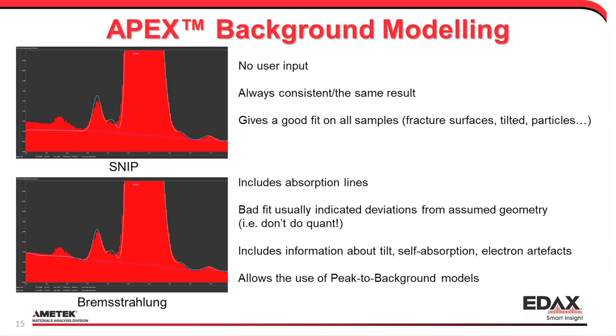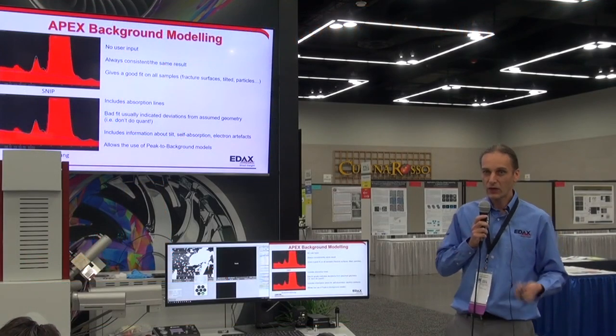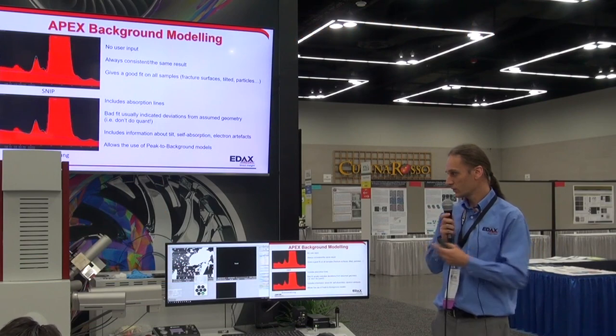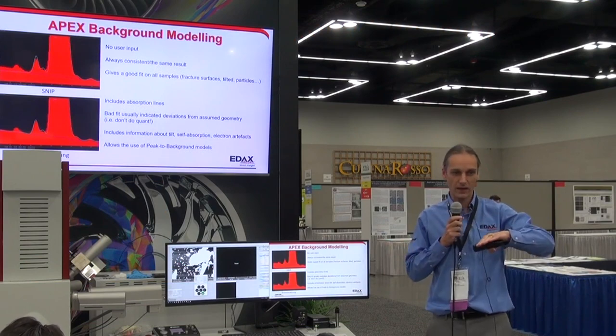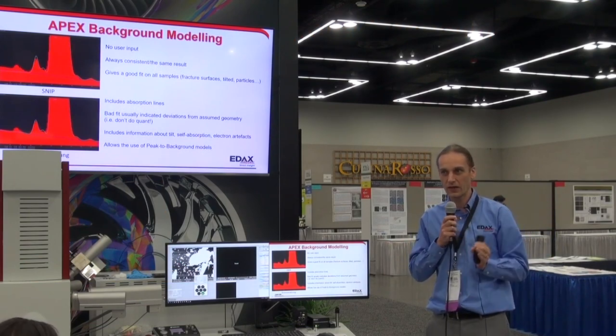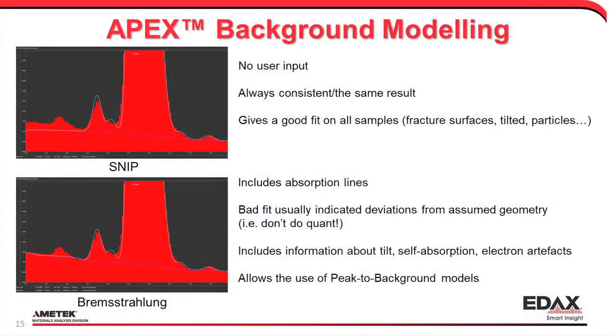The Bremsstrahlung, on the other hand, has absorption lines built in. If you get a bad fit, that means something is wrong — something is not meeting what we think it should be. If you have a fracture surface, the microscope might tell us the sample is flat, but a fracture surface will have all sorts of angles, leading to a deviation compared to the ideal model. The Bremsstrahlung has information about the sample tilt, electron artifacts, and sample self-absorption, and it allows us to use the peak-to-background model as well.